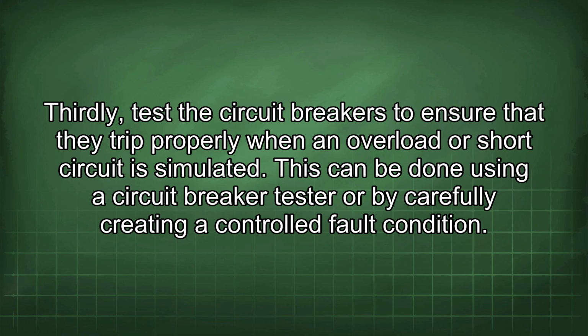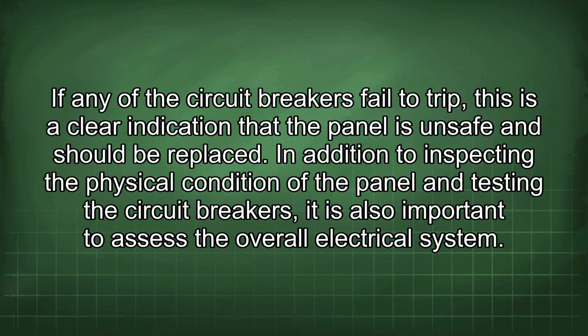Thirdly, test the circuit breakers to ensure that they trip properly when an overload or short circuit is simulated. This can be done using a circuit breaker tester or by carefully creating a controlled fault condition. If any of the circuit breakers fail to trip, this is a clear indication that the panel is unsafe and should be replaced.